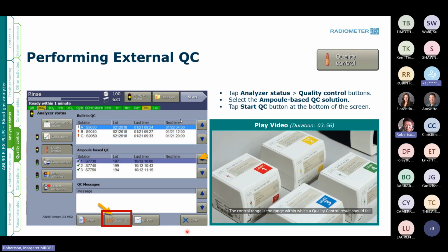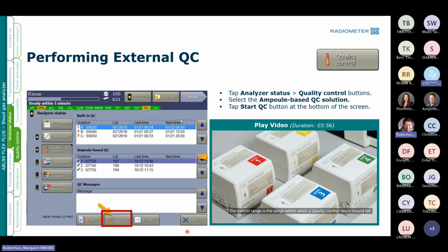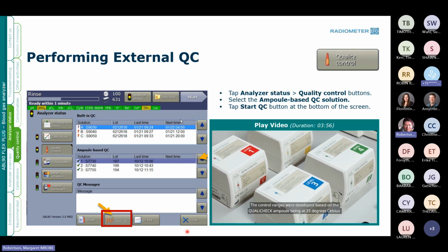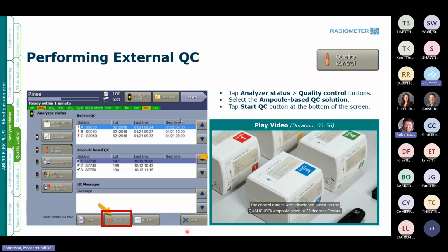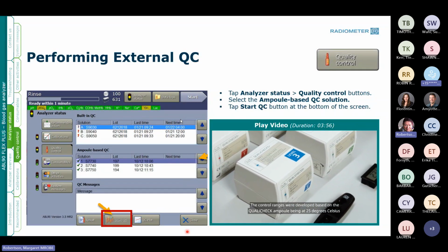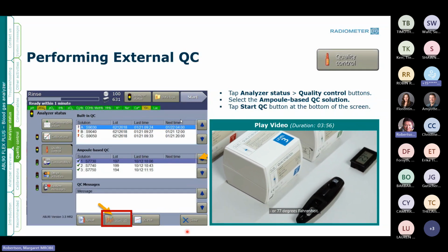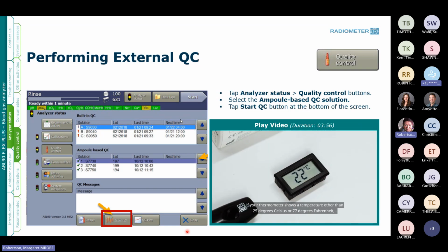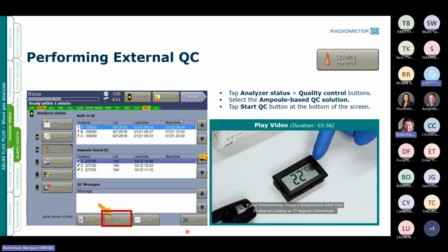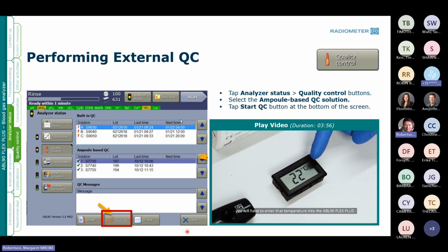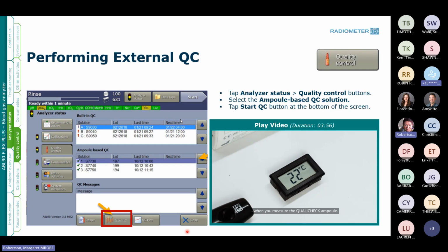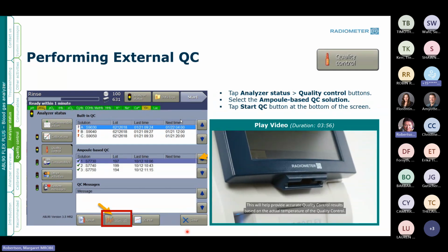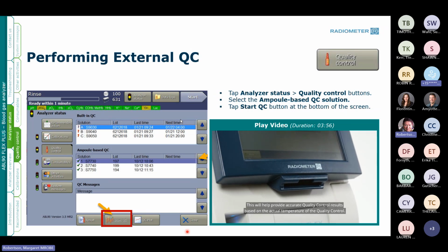The control range is the range within which a quality control result should fall. The control ranges were developed based on the QualiCheck ampoule being at 25 degrees Celsius, or 77 degrees Fahrenheit. If your thermometer shows a temperature other than 25 degrees Celsius or 77 degrees Fahrenheit, you will have to enter that temperature into the ABL90 Flex Plus when you measure the QualiCheck ampoule. This will help provide accurate quality control results based on the actual temperature of the quality control.